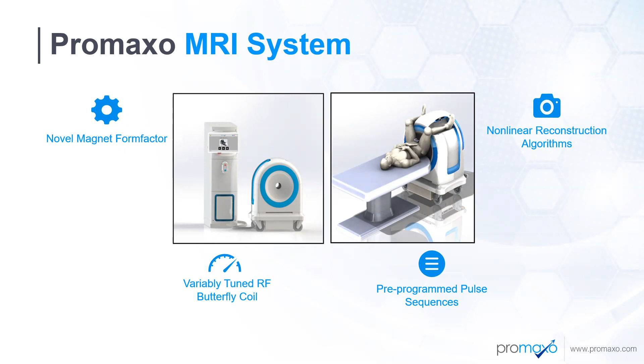The system has recently received FDA clearance for prostate biopsy navigation. Given its novel magnet form factor and small size, it can be placed in a physician's office. The system uses pre-programmed pulse sequences, making it easier for a physician to operate. Due to its field inhomogeneity, the system uses nonlinear reconstruction algorithms instead of the traditional Fourier transforms. The variably tuned receive coil allows the system to acquire multiple slices simultaneously.